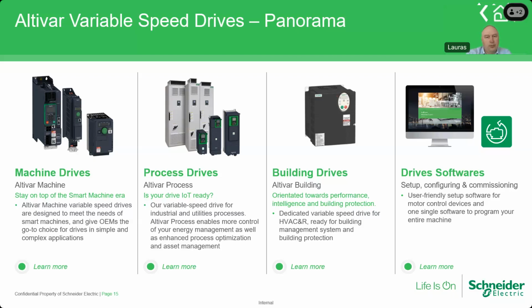Third range is building drives, so-called HVAC drives, more dedicated for buildings, for ventilators or pumps. Because for buildings we usually don't have an industrial environment, requirements for building drives are higher regarding filters installed in the drive, regarding EMC and harmonics, so they have lower harmonic level and lower EMC.